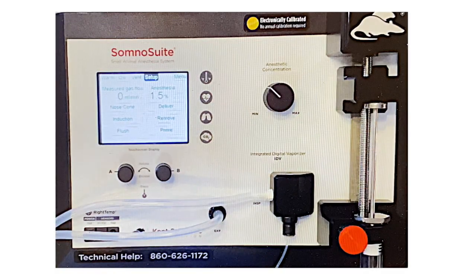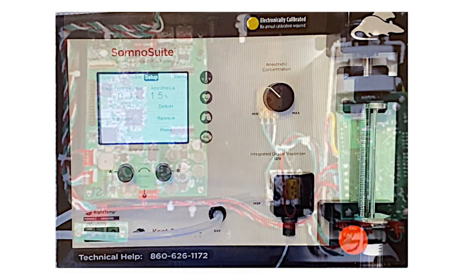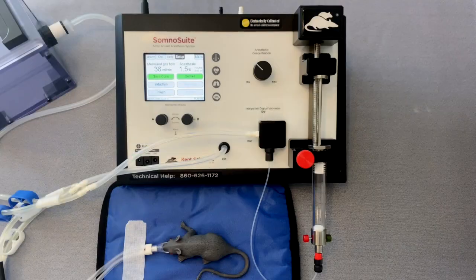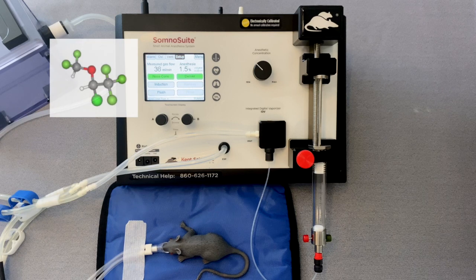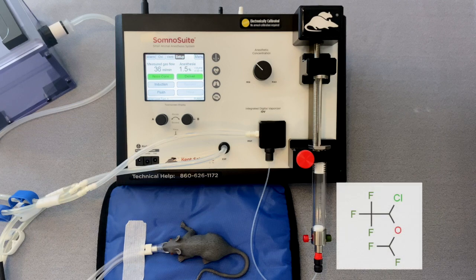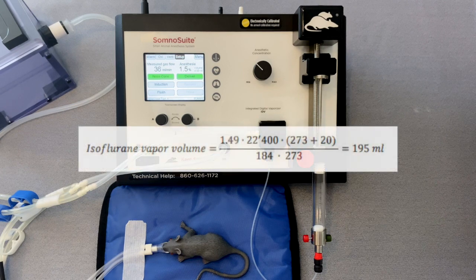The SomnoSuite provides vaporization and control of anesthetic delivery using solid-state electronics, hardware, and software. The SomnoSuite also uses an active vaporization system which precisely controls vaporization temperature. Vaporization, gas flow, and anesthesia delivery are closely monitored by electronic sensors that are controlled by computer algorithms rather than mechanical moving parts.